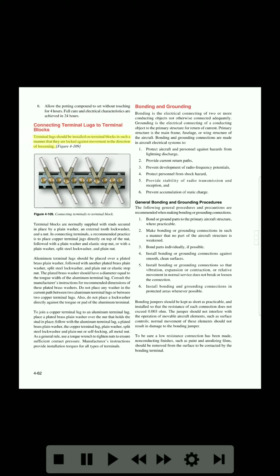Terminal lugs should be installed on terminal blocks in such a manner that they are locked against movement in the direction of loosening. Figure 4-109. Connecting terminals to terminal block. Terminal blocks are normally supplied with studs secured in place by a plain washer, an external tooth lock washer, and a nut.